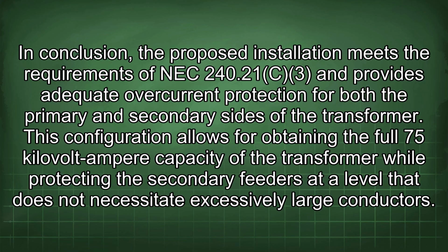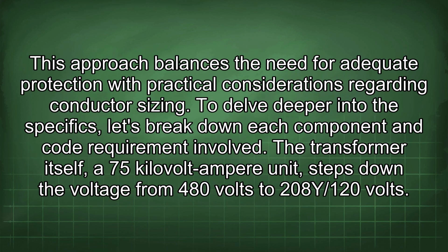This configuration allows for obtaining the full 75 kVA capacity of the transformer while protecting the secondary feeders at a level that does not necessitate excessively large conductors. This approach balances the need for adequate protection with practical considerations regarding conductor sizing. To delve deeper into the specifics, let's break down each component and code requirement involved.